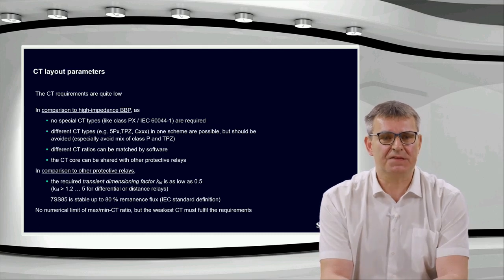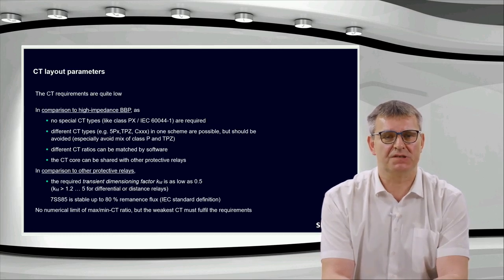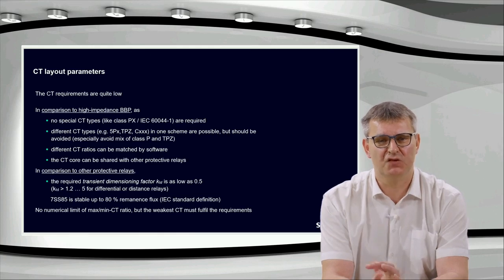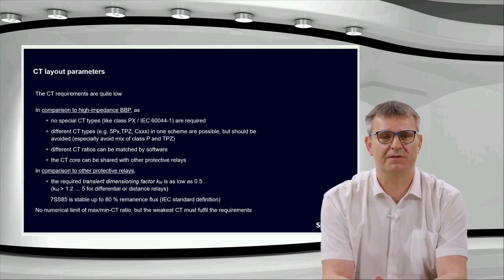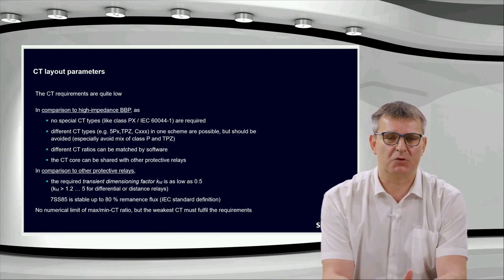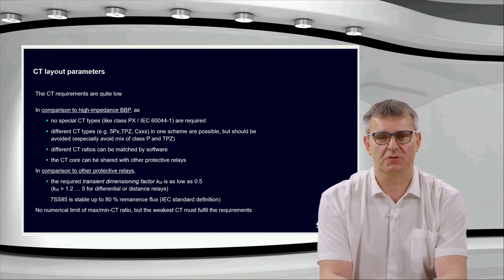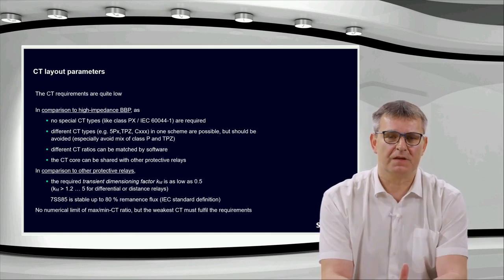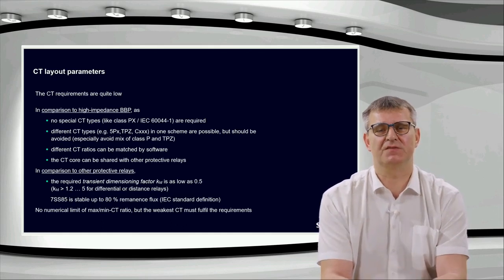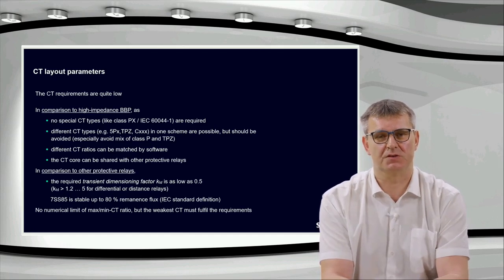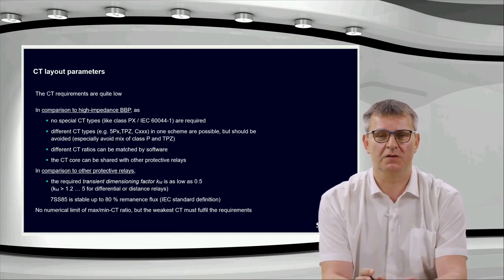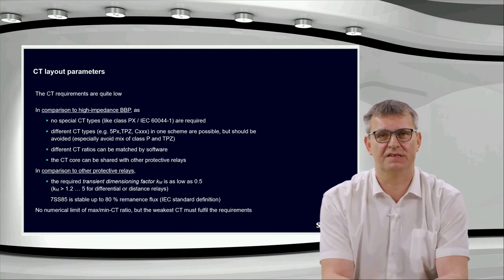This is also a quite often asked question, and we have no numerical limit between the highest and the lowest, the maximum and the minimum CT ratio. But even the weakest CT must fulfill the requirements. That is important, so that really all the different CTs used must fulfill the CT requirements. The CT requirements I will explain in the next slides.